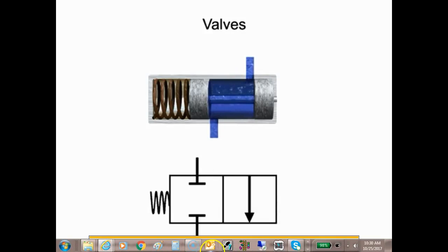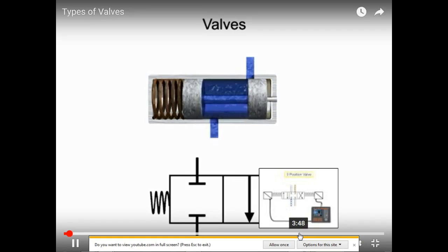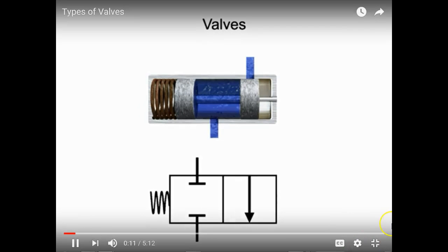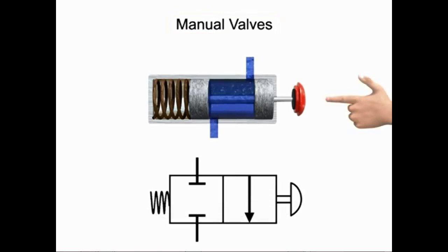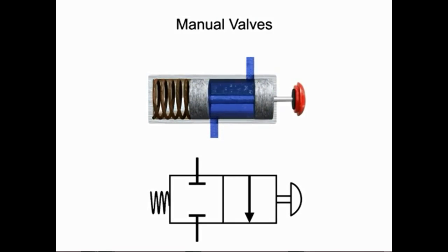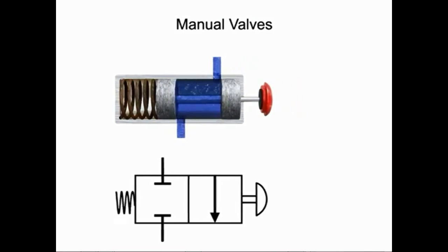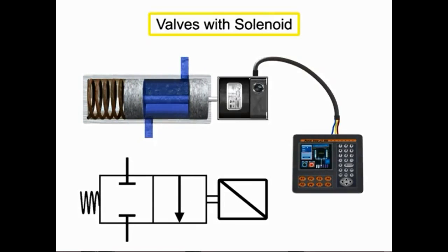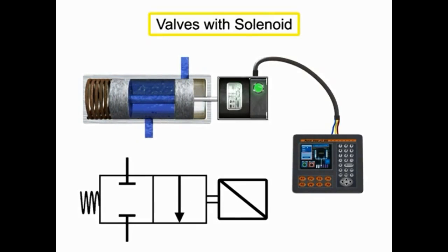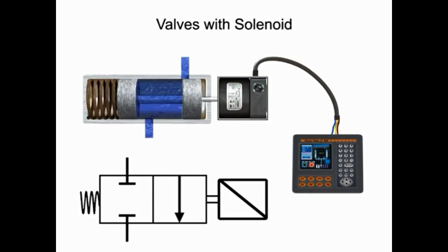In most air and hydraulic fluid power circuits, valves are used to control the direction, rate, and pressure in fluid lines. Control valves for these functions can be purchased with either manual or solenoid actuators. In a manually actuated valve, the internal cylinder is shifted by hand using a lever, push button, plunger, or other manual actuating device. By contrast, valves with a solenoid actuator respond to an electrical signal for shifting. With electrical control, machine cycles can be set up for automatic sequencing, and operator control can be exercised from a remote location.